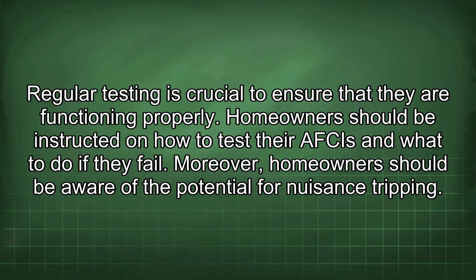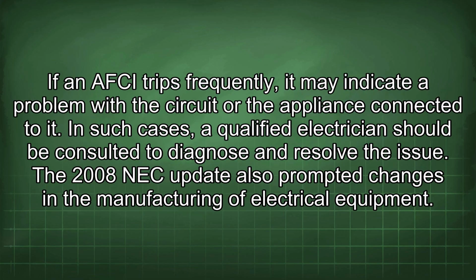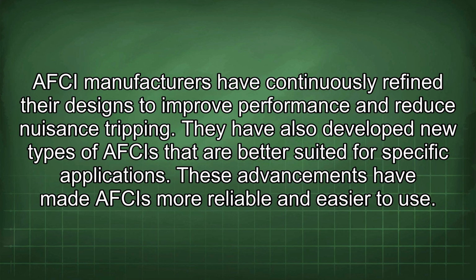Moreover, homeowners should be aware of the potential for nuisance tripping. If an AFCI trips frequently, it may indicate a problem with the circuit or the appliance connected to it. In such cases, a qualified electrician should be consulted to diagnose and resolve the issue. The 2008 NEC update also prompted changes in the manufacturing of electrical equipment. AFCI manufacturers have continuously refined their designs to improve performance and reduce nuisance tripping. They have also developed new types of AFCIs that are better suited for specific applications. These advancements have made AFCIs more reliable and easier to use.